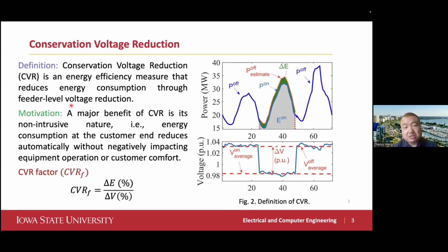I reduce it—I change the tap and reduce the voltage at the substation a little bit. Certainly, you want to make sure the end-of-line voltage, or everywhere in your feeder, stays within the standard, the ANSI standard of 120 plus or minus 5%.